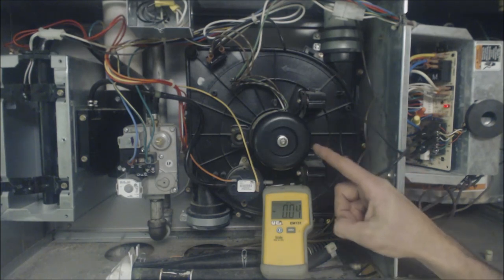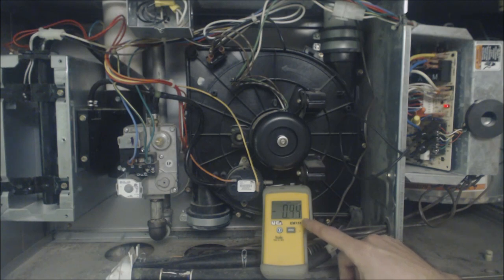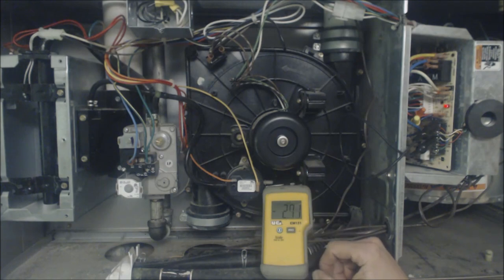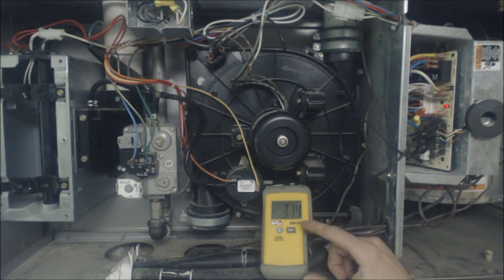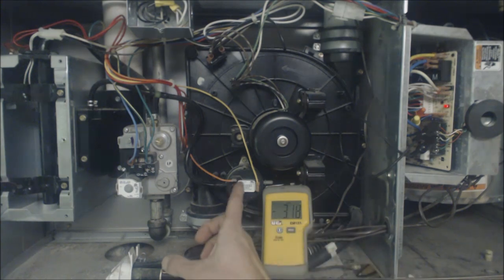So your inducer motor is turning on and now we're getting a negative inch water column reading, okay, so it's inches of water column.